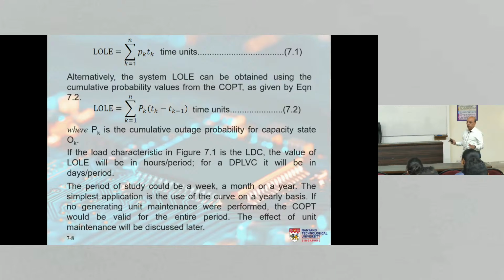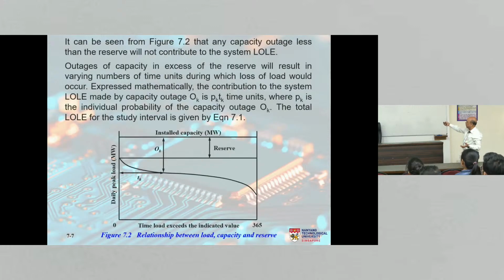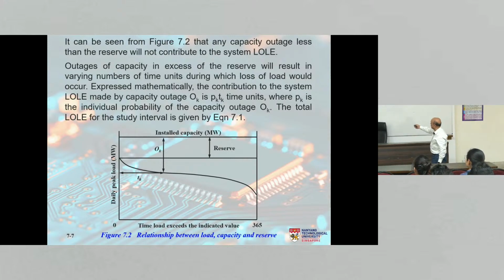Very straightforward. You know the probability of each outage, don't you? From the capacity outage table, you already know Pk. You need to find Tk using this sort of a notation. So whenever there is an outage, you find the time units that we are not able to supply the load, either using software or using the equation of the straight line, or any other format in which the load curve is given to you, okay? It's not an instant, it's a period. We are not able to supply the load for this period, correct?